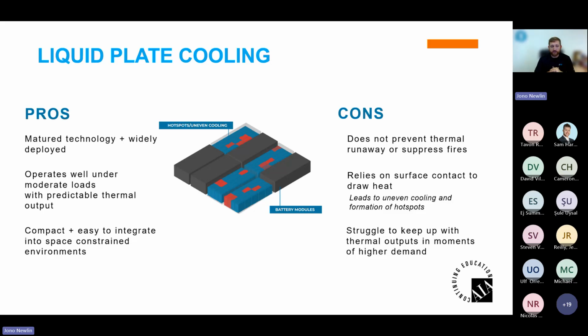And it's compact and easy to integrate into space-constrained environments. We don't have to have these big aircon units blowing over the cells. We're able to fit those in. You have a heat exchanger, you have your pumps and whatnot to be able to move the liquid glycol. Some cons. So this does not prevent thermal runaway or suppress fire. So it controls temperature, but you can still have a cell that goes into thermal runaway.